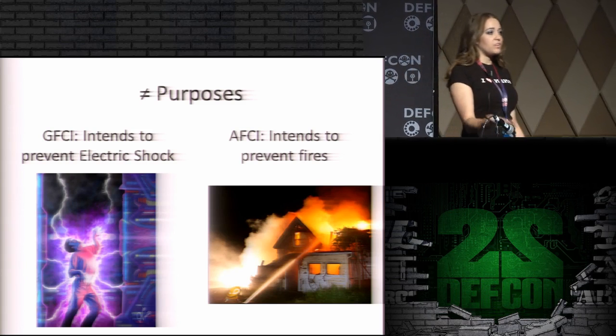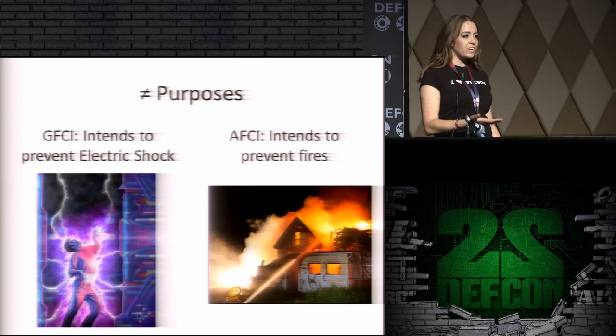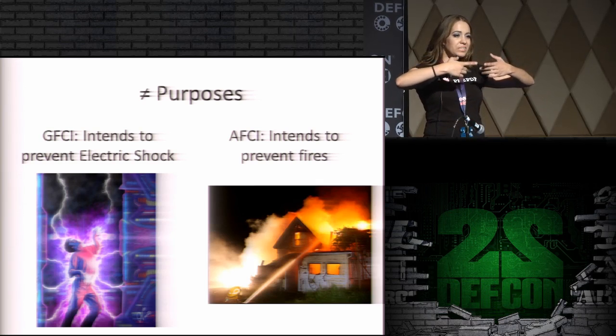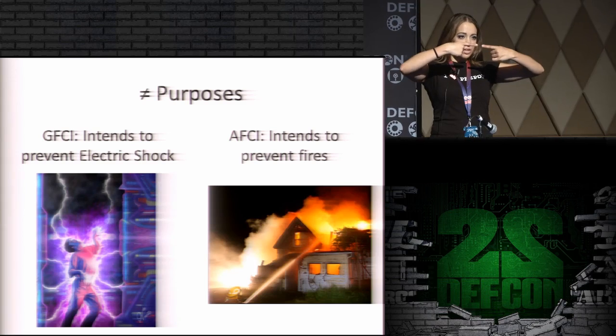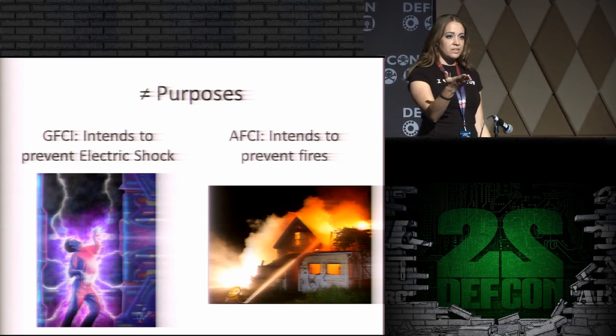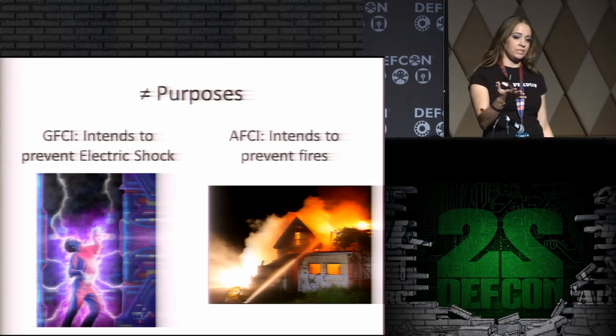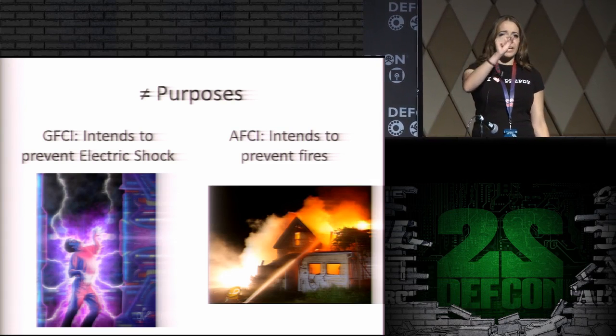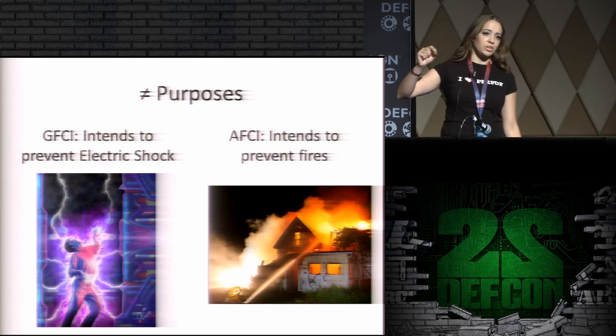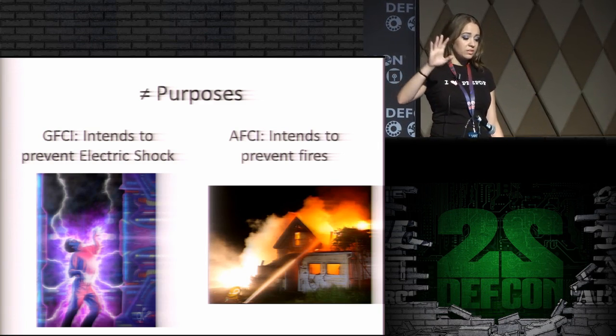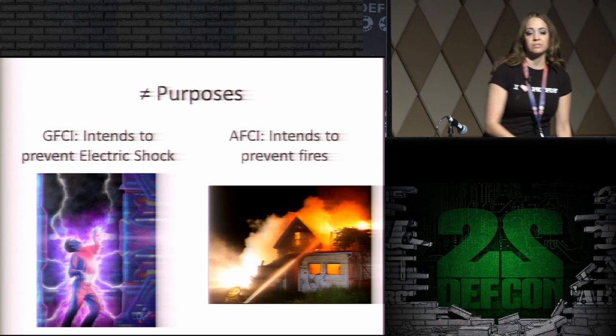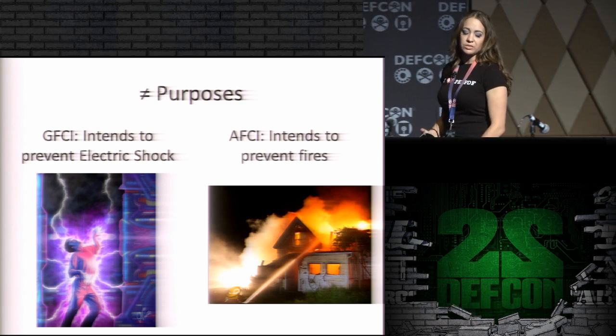It has to be really specific and really quick. That's what GFCIs do. AFCIs, on the other hand, are trying to protect your house from catching fire, like from worn out old cables if there's a spark anywhere. They find it by analyzing the waveform of the alternating current, which has to be smooth. It's a much more complex piece of equipment than a GFCI.